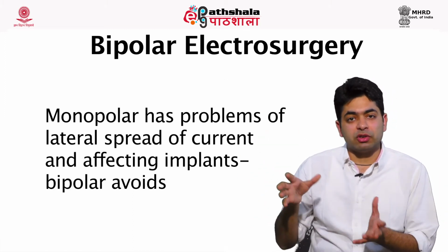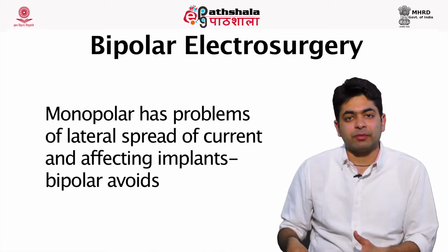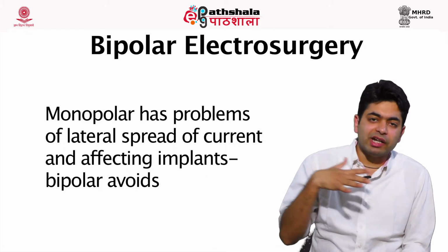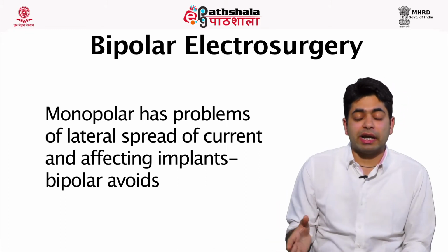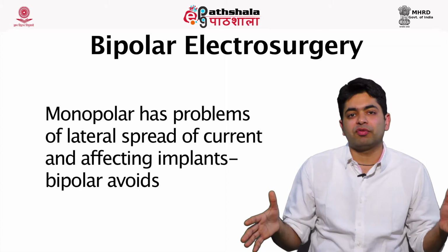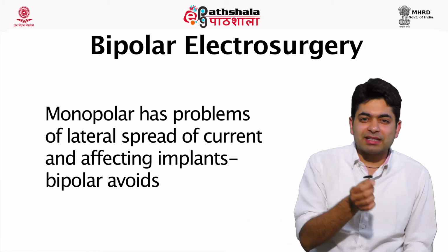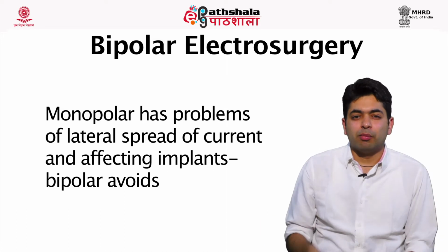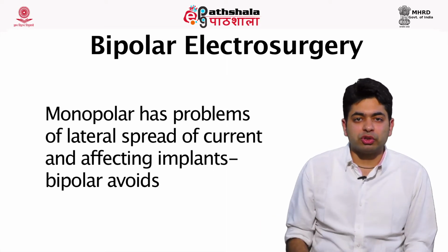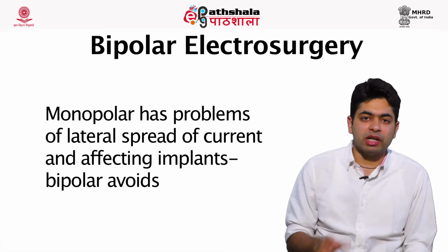of the circuit. So what if there are implants or electrosurgical instruments otherwise implanted into a person? Also, when we are using monopolar electrocautery, there is lateral spread of current into the tissues and it creates a large thermal spread of temperature. So for areas like the brain, where we cannot afford this lateral spread of temperature, monopolar electrocautery is not a good choice. Here we are using bipolar electrocautery.